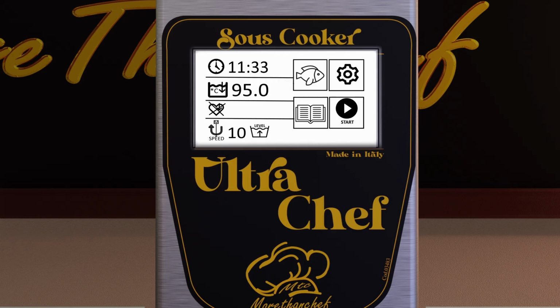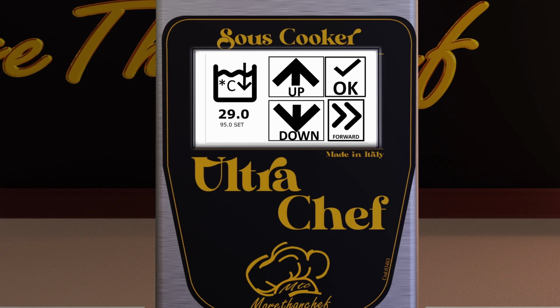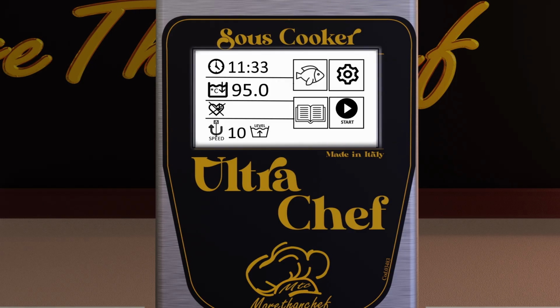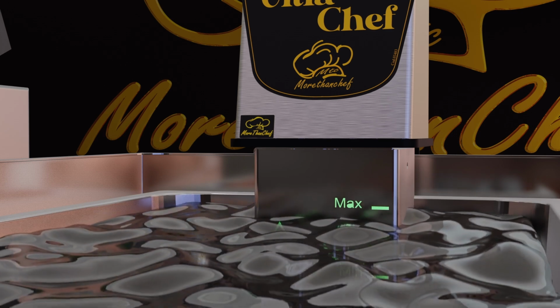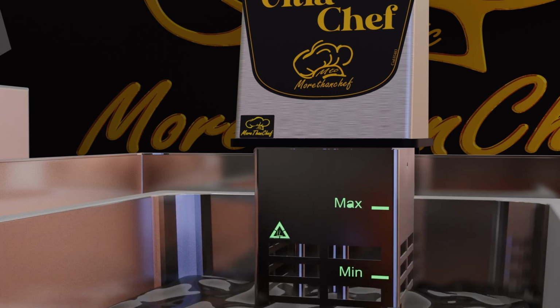To start a work cycle, follow these steps. From the main screen, press the recipe button to access the settings. Set the time, temperature, core probe if activated, and the fan circulation speed. Remember, after each setting, always press the OK button to save the data before moving on to the next parameter. Once all the parameters are set, the system will return to the main screen. Before pressing start to begin the cycle, check that the water level in the tank is sufficient and falls between the minimum and maximum marks indicated on the fan cover.